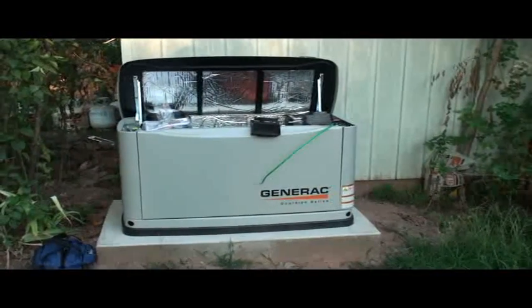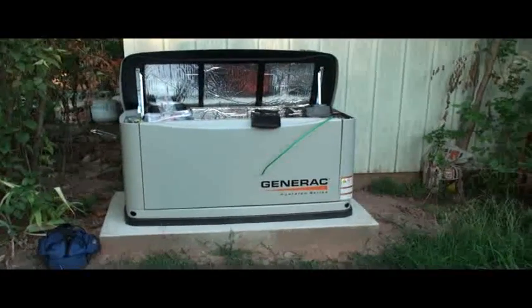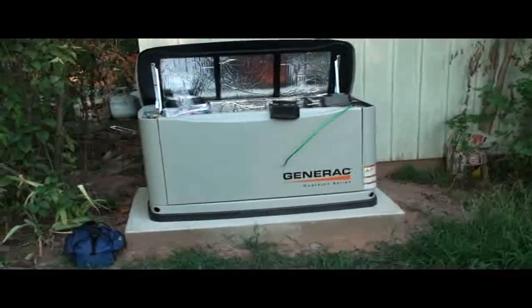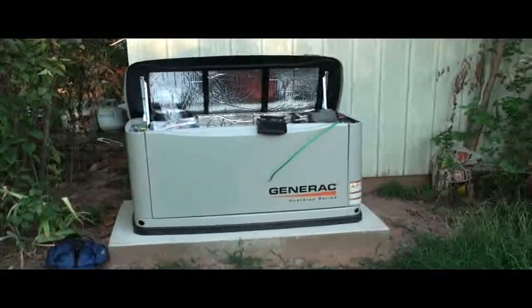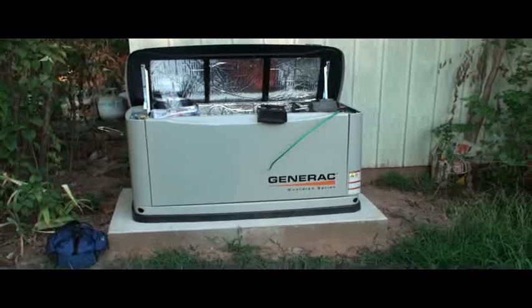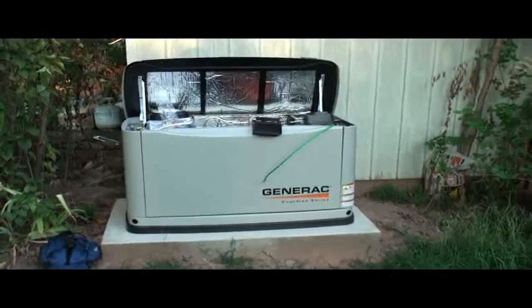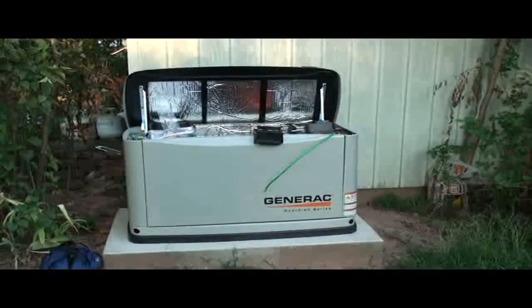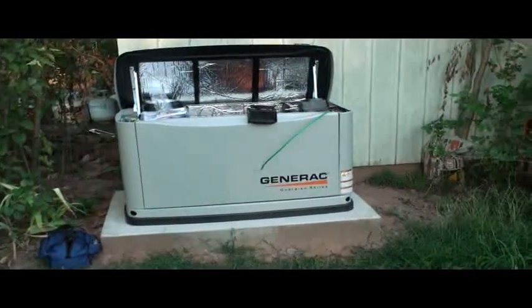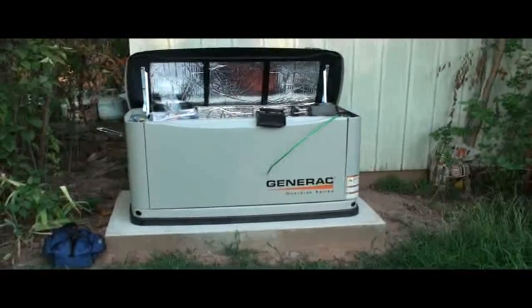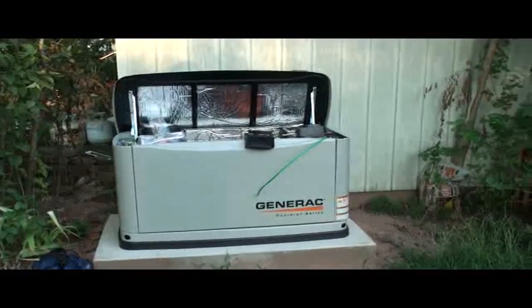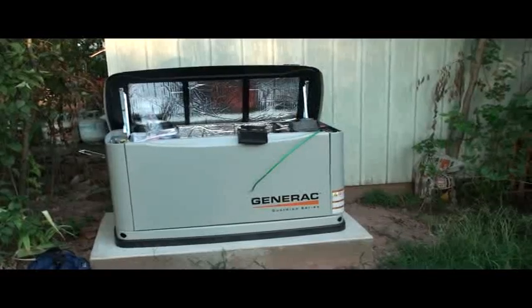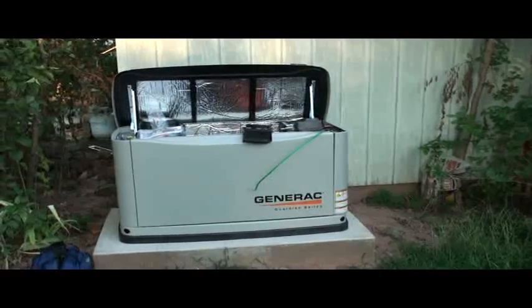My generator is installed about 100 feet from my electric panel, and according to the spec sheet, I looked at everything on there and I decided to run number four wire. It was the smallest size wire that the transfer switch would support, and it seemed to be the largest size that the generator itself would support.